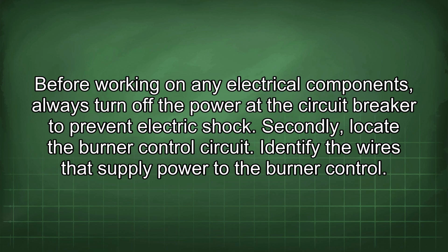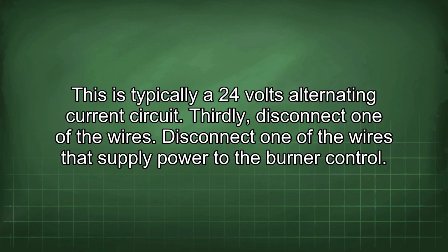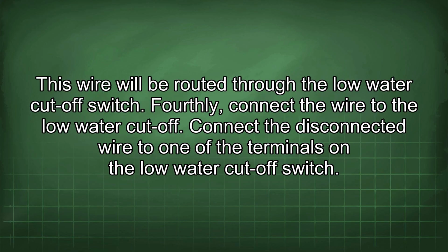Secondly, locate the burner control circuit. Identify the wires that supply power to the burner control. This is typically a 24 volt alternating current circuit. Thirdly, disconnect one of the wires. Disconnect one of the wires that supply power to the burner control. This wire will be routed through the low water cutoff switch.